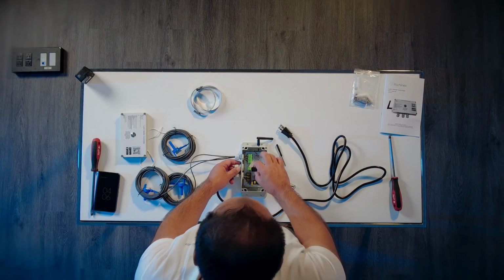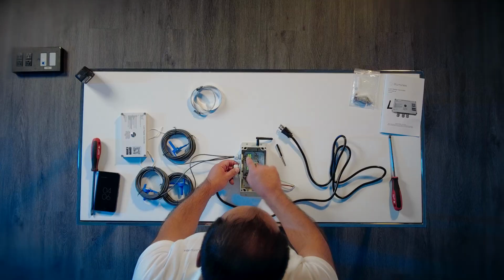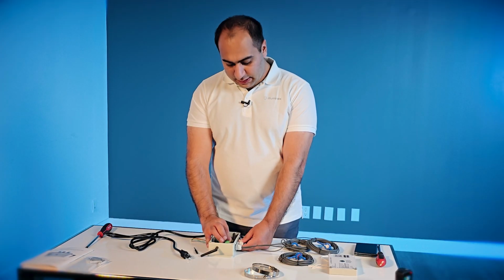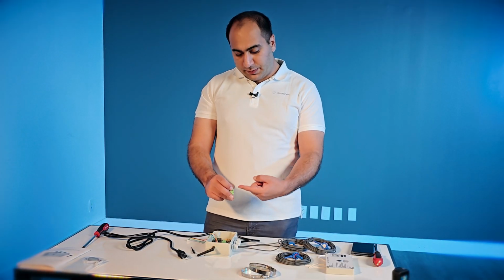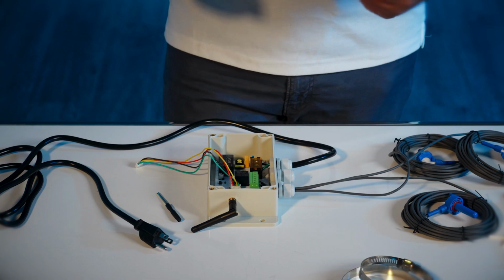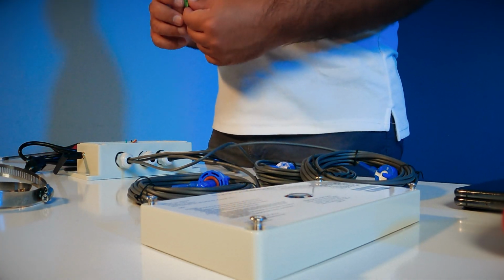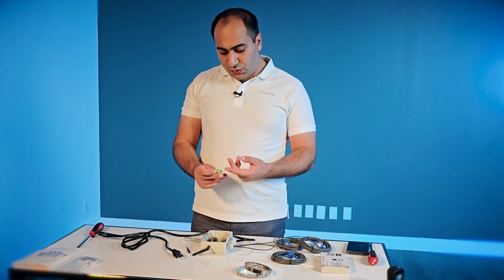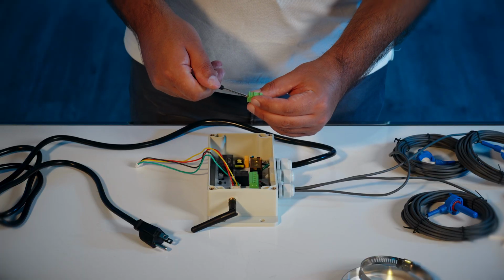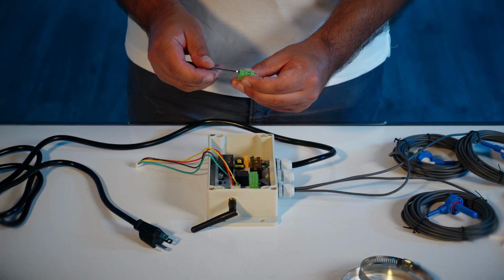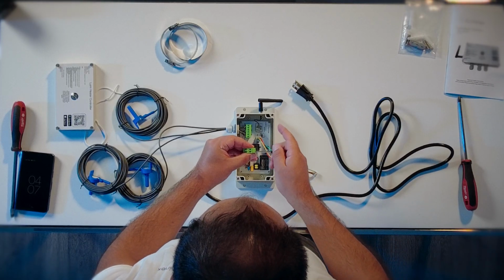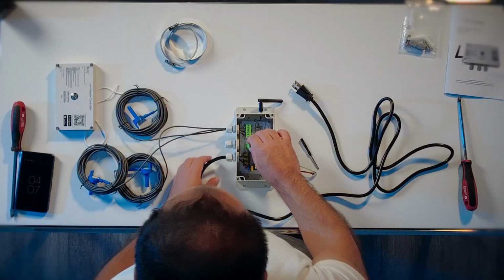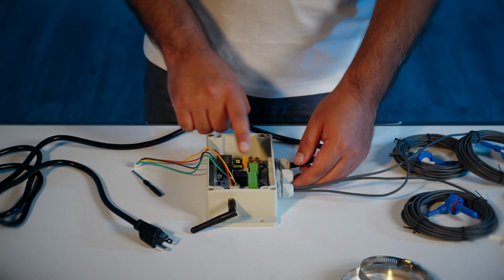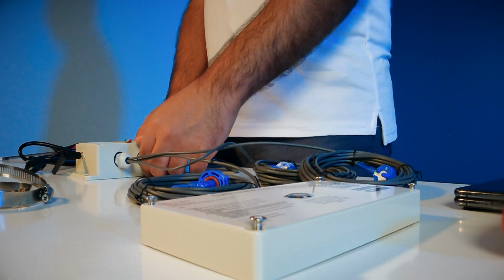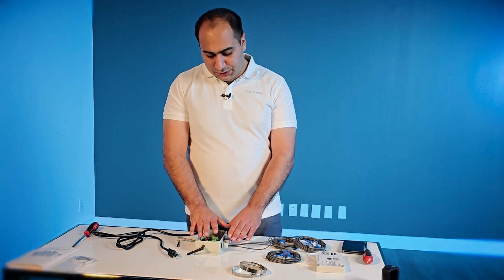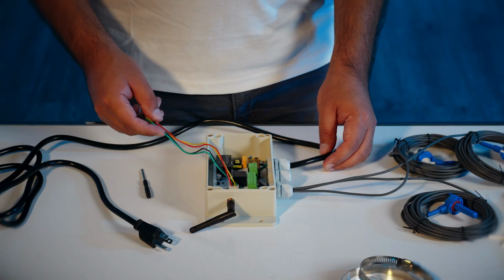The next connection is our heater dry contact connection. Similar to the temperature sensors, the dry heater connection can be removed. The dry heater wire will be coming from the heater. Refer to your owner's manual from the heater's manufacturer to figure out how to connect this dry contact wire. But it would be a 2-wire cable. You'd have to bring it in, open up the screws on the terminal, just like the temperature sensors, and once the wire is installed, reinstall the terminal and close the liquid tight connector. So once that's done, you are done with the hardware setup of the heater controller.